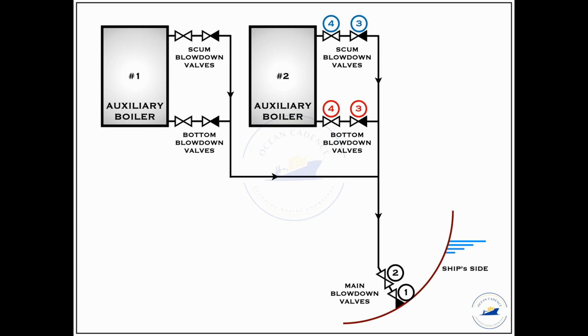Usually the blowdown is always carried out at sea, and it also helps us in a way that we maintain the freshwater log enough, so that if the freshwater consumption is high during the boiler blowdown, we can still top it up and have freshwater batches ready for further process. I hope that the video gives you a clear idea of why the blowdown is required and how we carry out the blowdown and maintain our boiler in a healthy condition, and also make sure that all the test result values are always under limit.